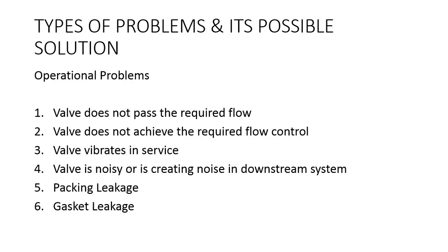Fourth, valve is noisy or is creating noise in the downstream system. Noise can be generated due to mechanical, hydrodynamic and aerodynamic origin. Mechanical noise can be due to wear in the trim parts; simply replace the trim parts. Hydrodynamic noise can be generated due to cavitating liquid or high velocity of the liquid flow. Check the type of trim and, if required, special trim needs to be used instead of the general trim.